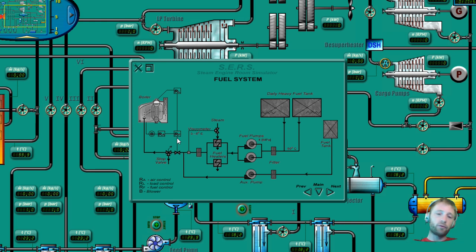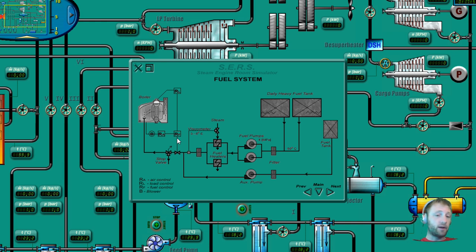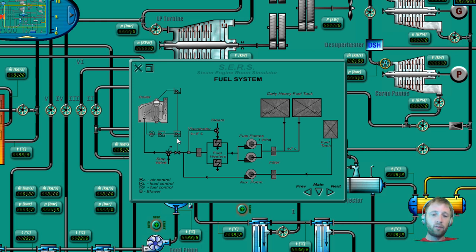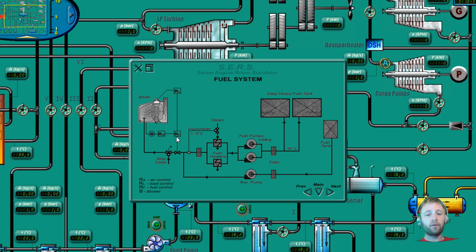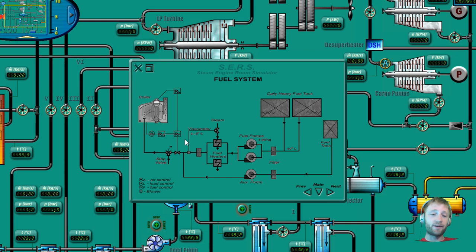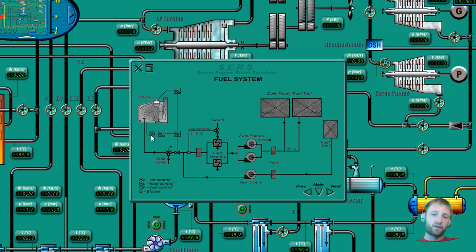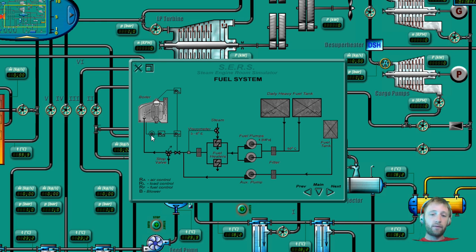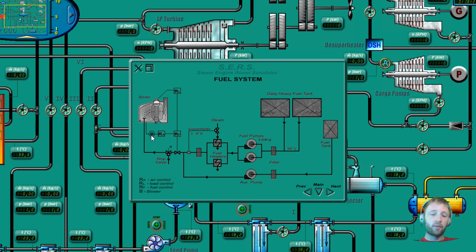And then they will remain there. If the set point will be changed, these controllers will give additional fuel to increase or to decrease until the set point will be achieved. At the point when set point will be achieved, a signal will be sent to air controller and fuel controller to remain locked there in appropriate position for the load desired. We have also our blower which supply air to our boiler, and this is the most important things that a boiler needs: it needs air, fuel, and proper regulation.